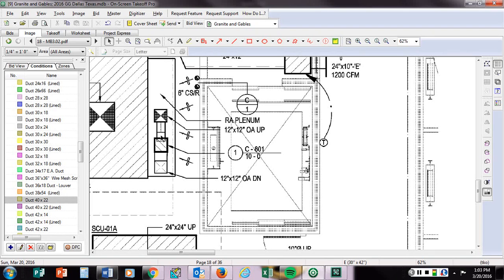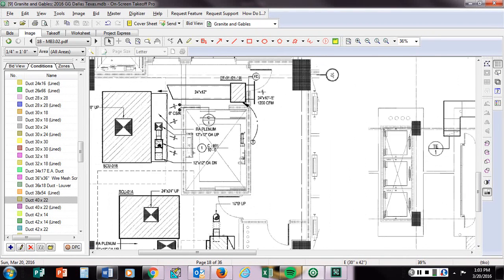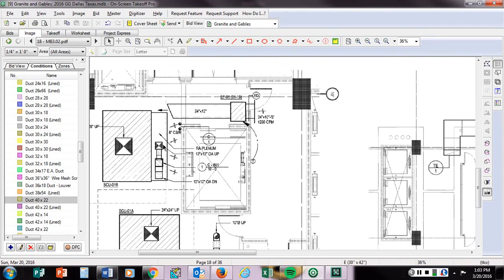Now they put VAV boxes on this job strictly because they wanted to have an accurate record of how much outside air was being brought in for ventilation. Every VAV box has an analog input on the control side that could read flow, and they'll be able to document the amount of CFM, and they'll be able to control the amount of CFM. There's all kinds of control strategies out there, if you happen to know, based on CO2 levels in the space.